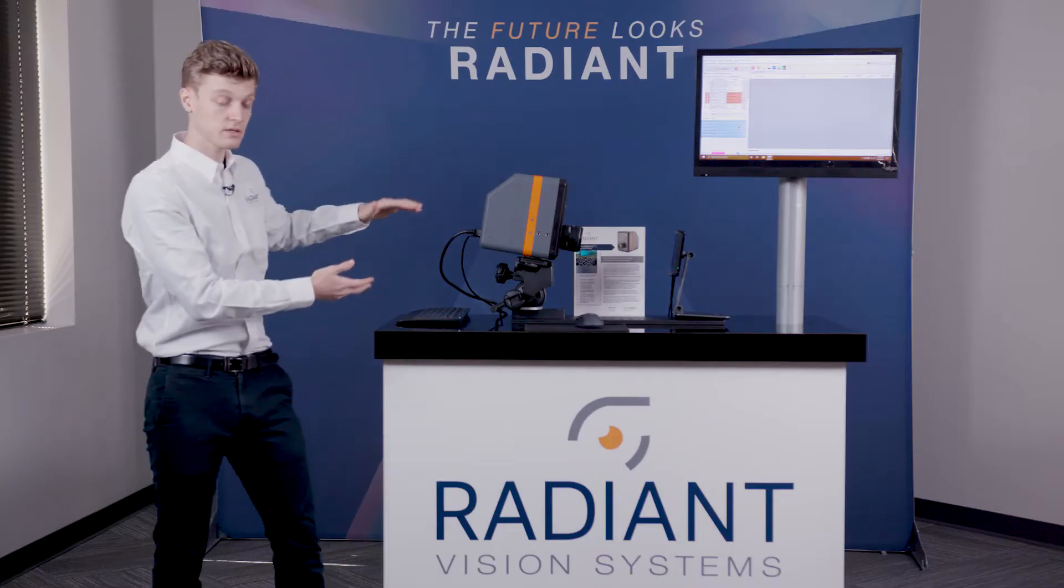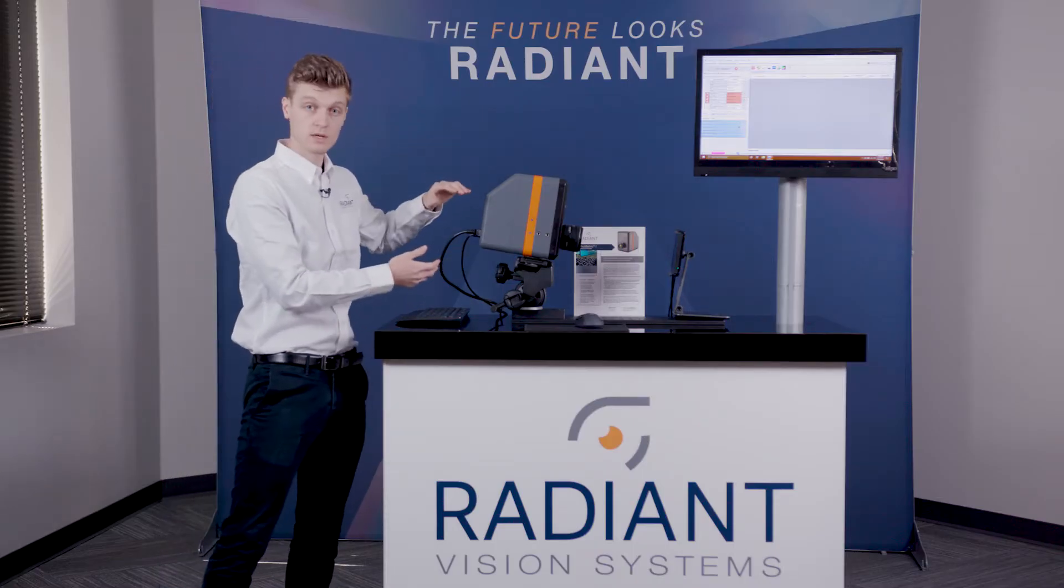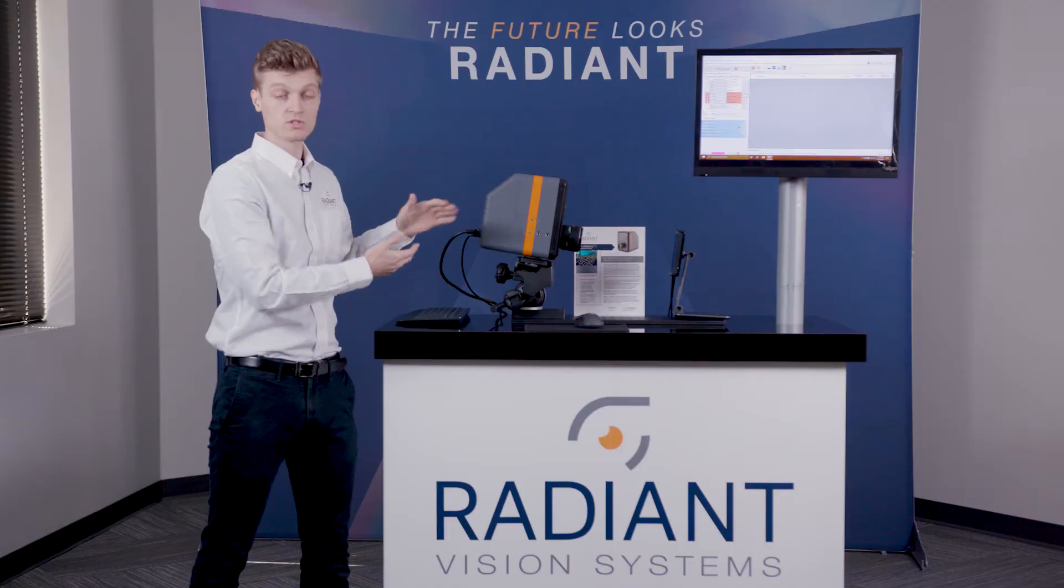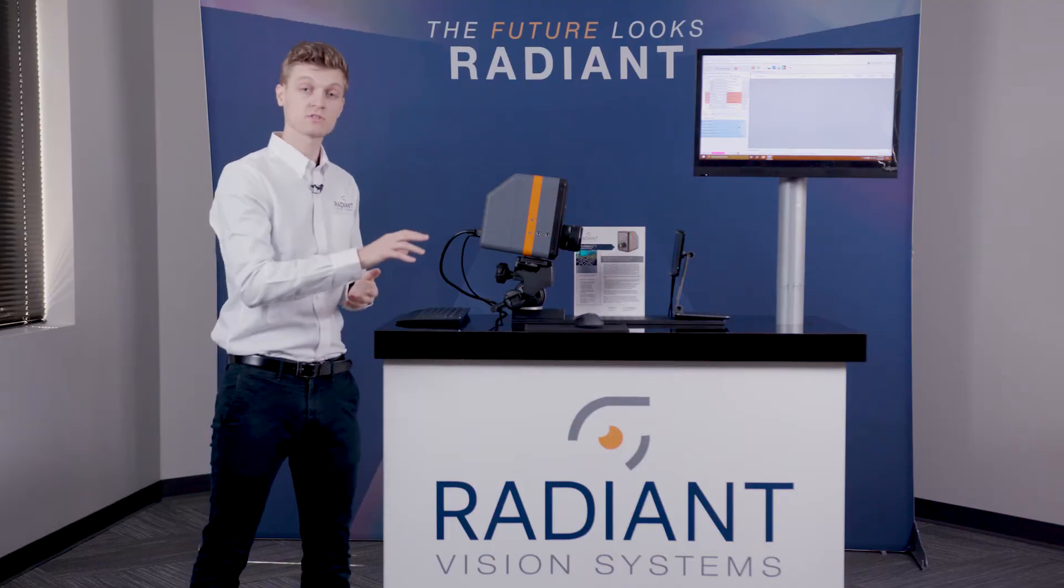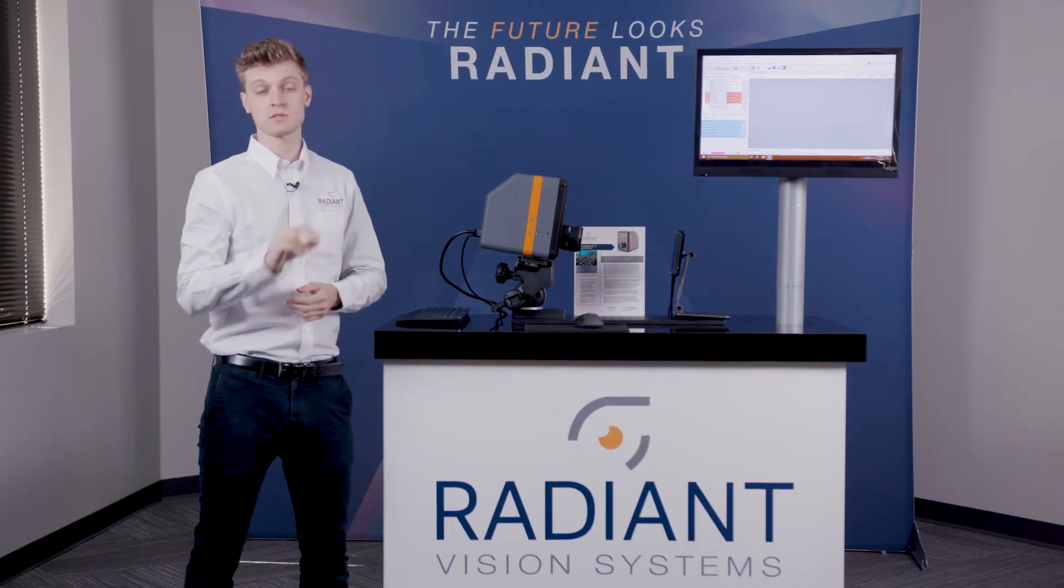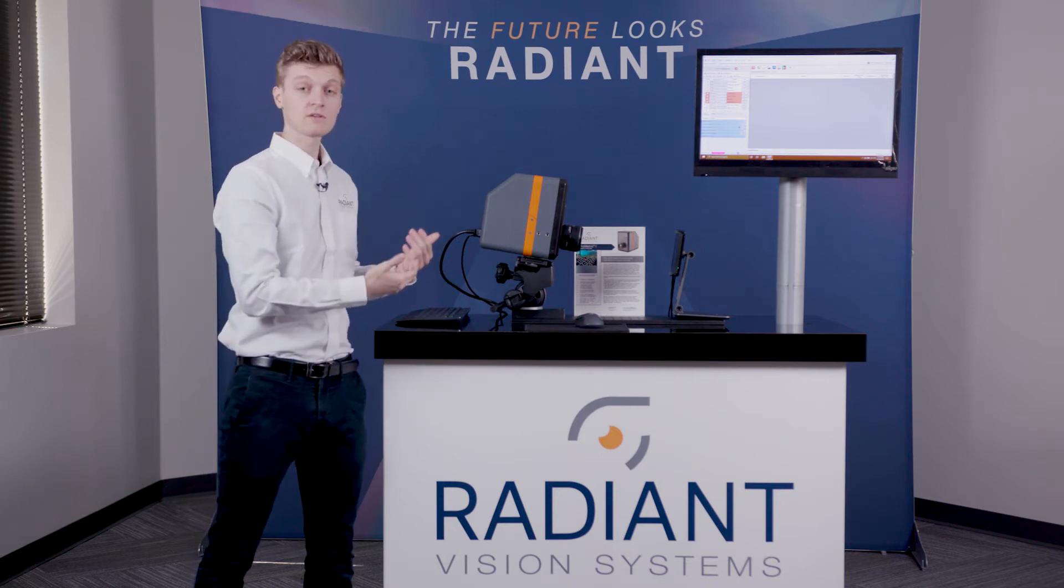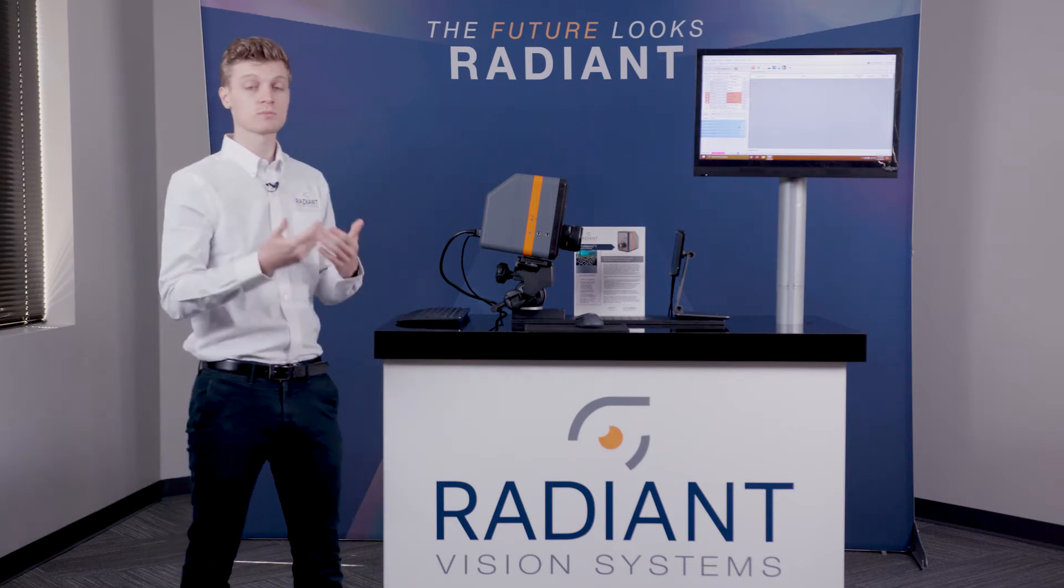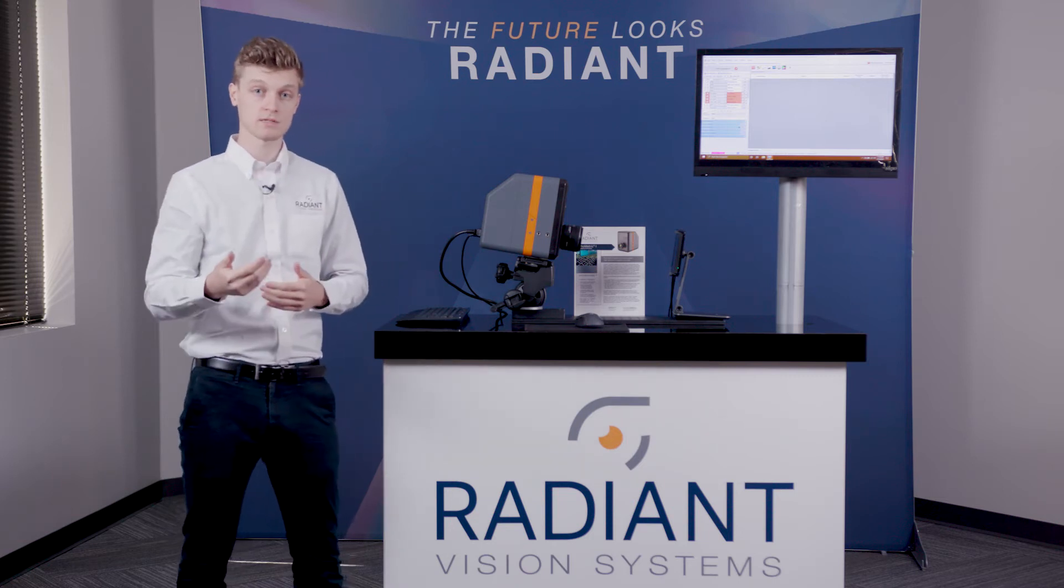This particular system right here is a scientific metrology unit. What that means is we're going to be able to measure the luminance and color of a display. This particular system uses tri-stimulus filters. These filters are designed to replicate the response of the CIE color matching functions and what that allows the system to do is capture data that represents the human perception of color and brightness.